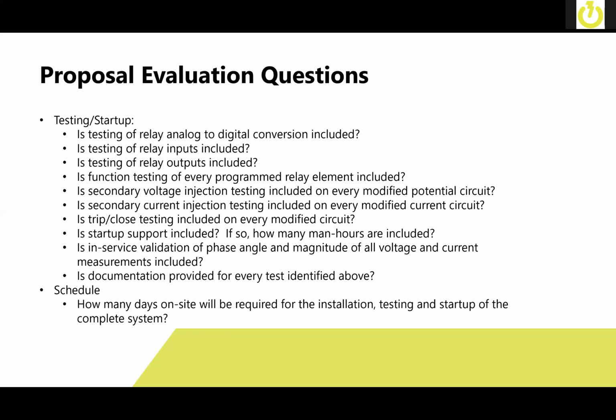Secondary voltage injection testing on all modified voltage potential circuits in the field. Secondary current injection testing on all modified current circuits. Trip close testing included on all modified circuits. Is startup support included? If so, how many man hours are included? A lot of times it'll be said that you need to get it started up within a certain amount of time after the completion of the retrofit. That may not be able to be performed due to how your system is set up or the outage that's in place. Is in-service validation of phase angle and magnitudes of all voltage and current measurements included, to ensure that you're getting the proper signals and everything's measuring correctly?